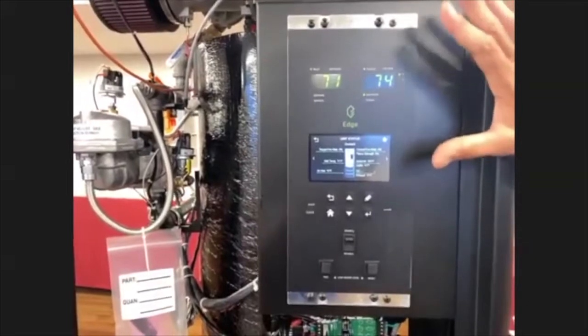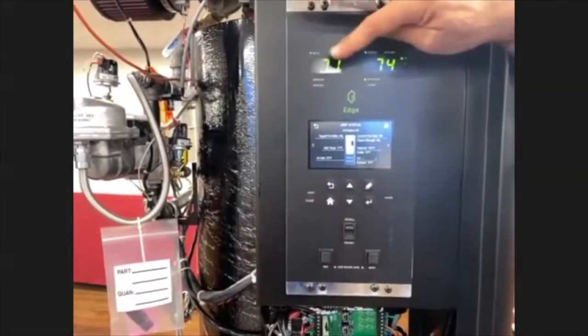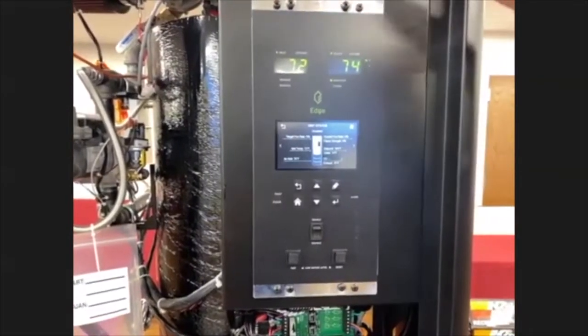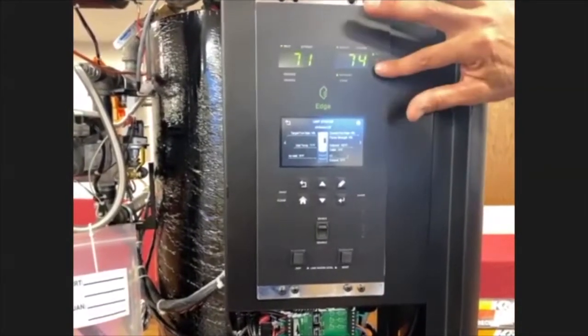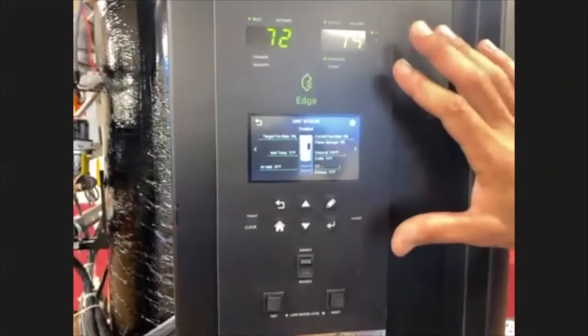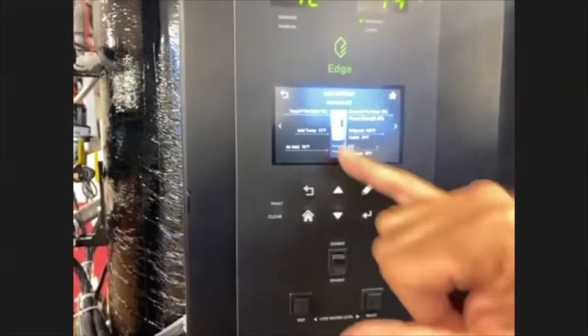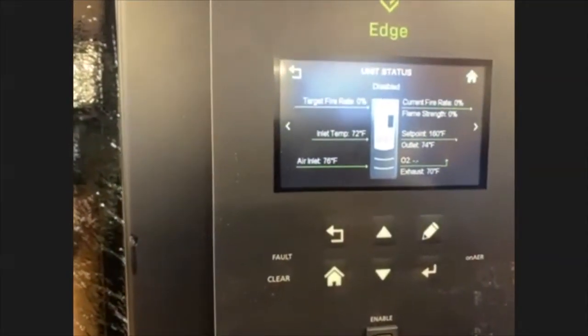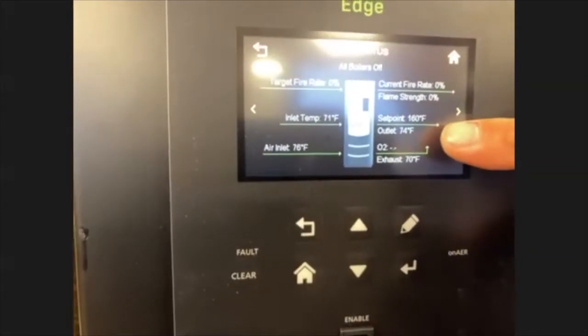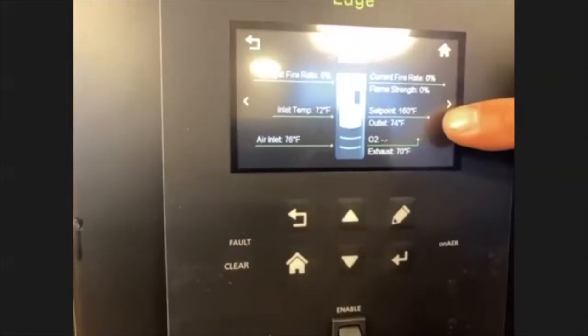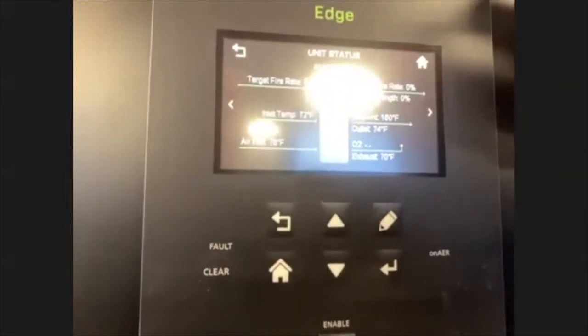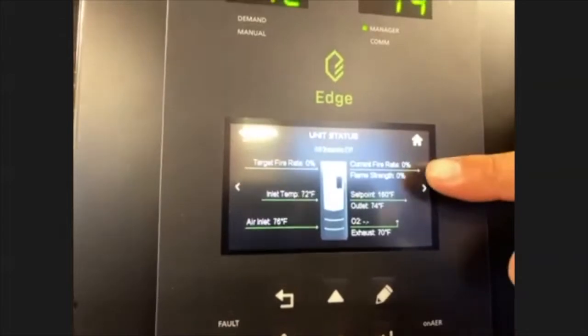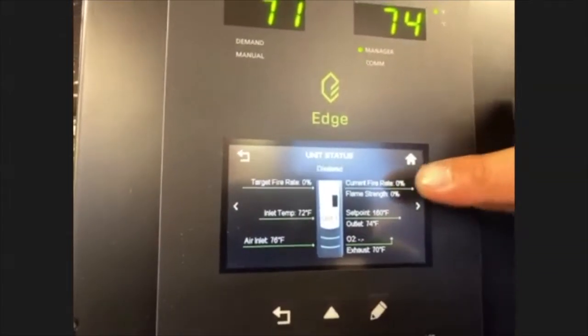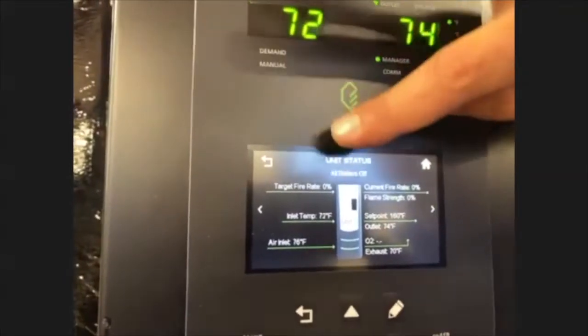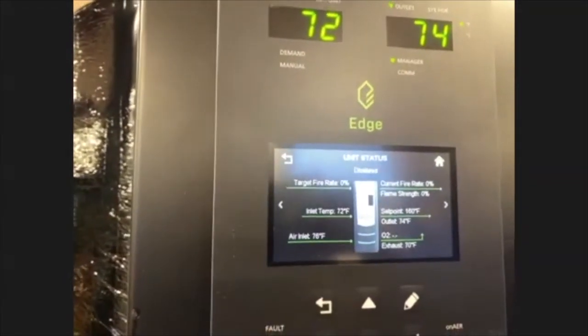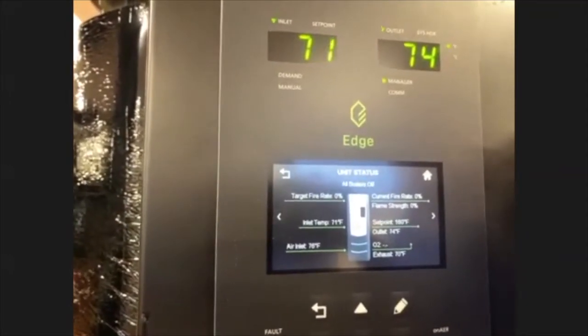And from the display, you can actually see several things. Our inlet temperature, water inlet temperature. Of course, we don't have any water coming in, but currently 72, and our outlet is 74. Some of those are also on the screen here as well. You can see the inlet temperature of 72. Outlet is 74. We currently have a 160-degree set point. The boiler obviously is disabled. As you can see, it says all boilers off. Our current firing rate is 0%. Our flame strength is 0%. Our target rate is 0%. That's because the boiler is not energized right now and it's not firing.